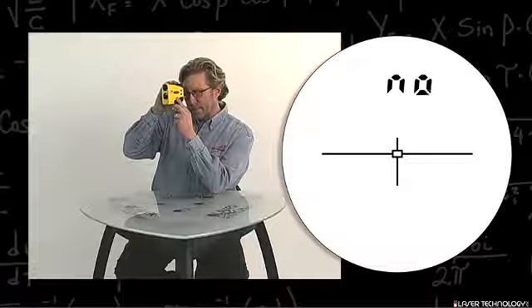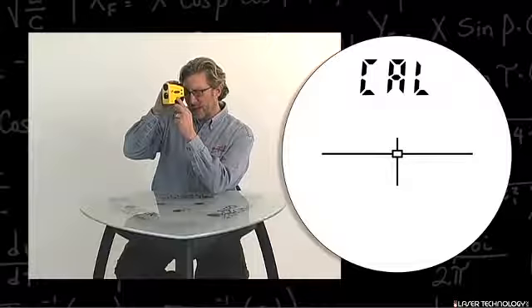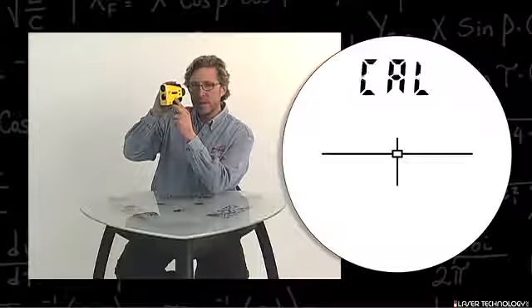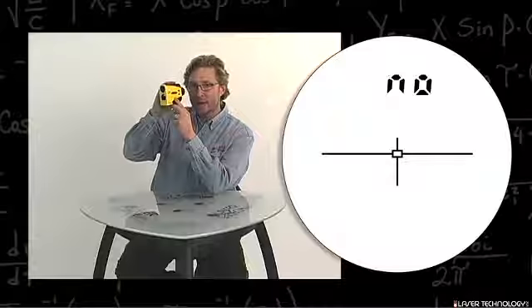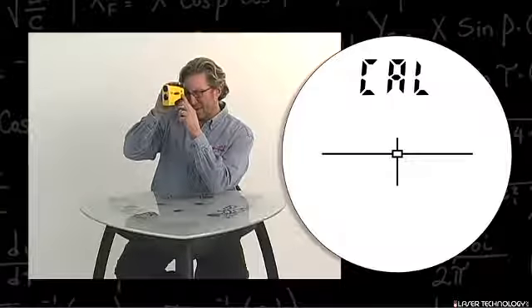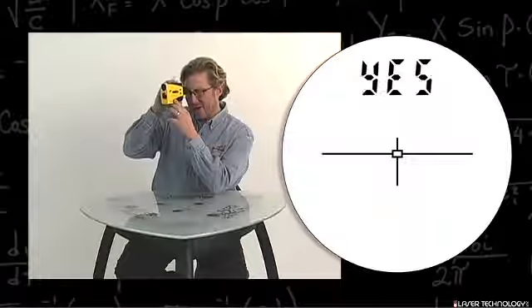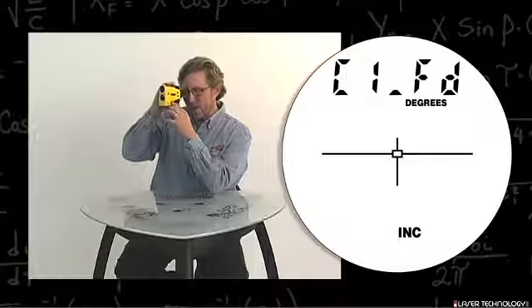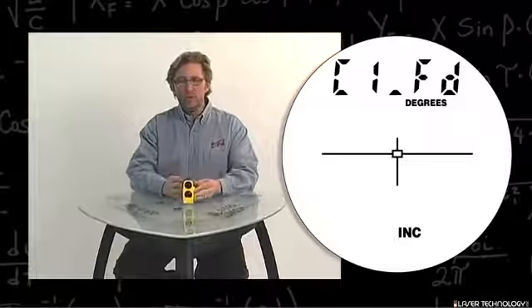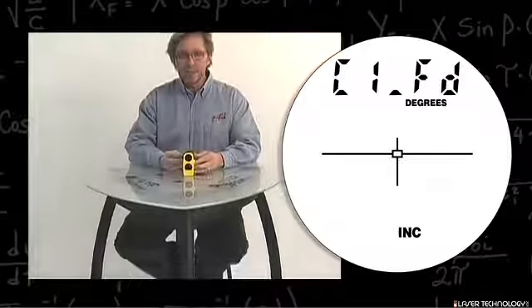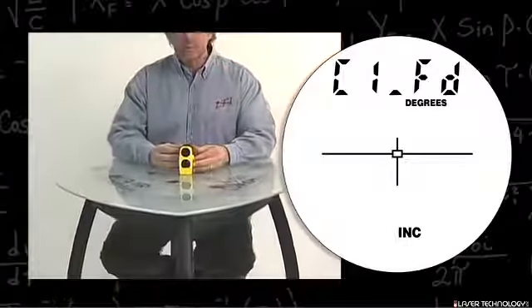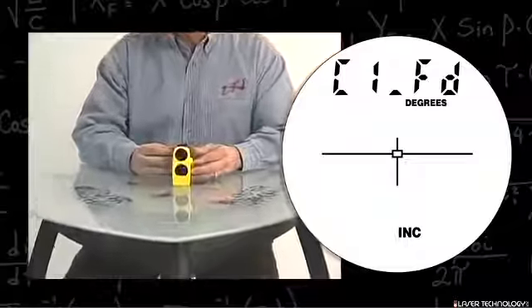Hit your fire button and it will say no cal. This is the opportunity that we have to back out of the calibration routine. We're going to hit the down arrow so that it says yes cal and hit your fire button. What comes up on the screen are the letters C1_FD for forward. This is the first position of the calibration routine.